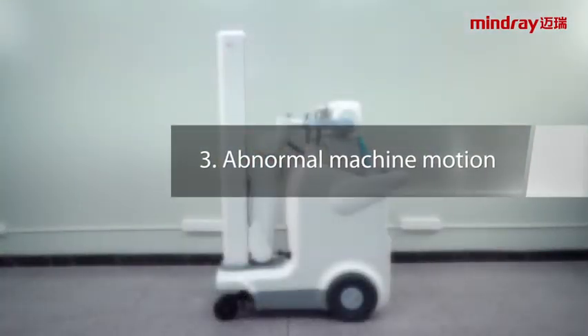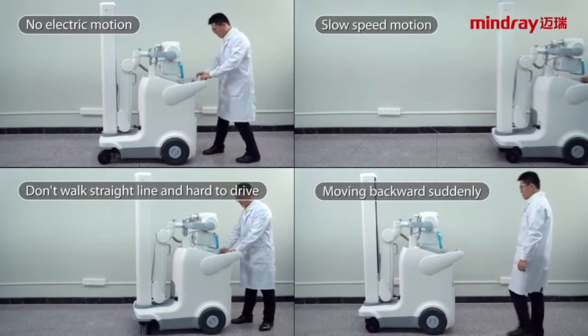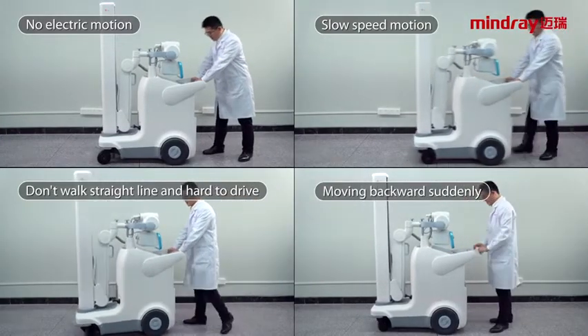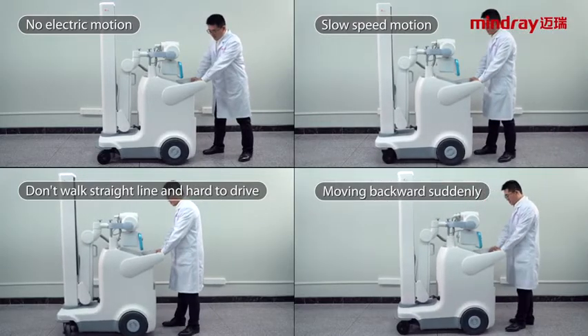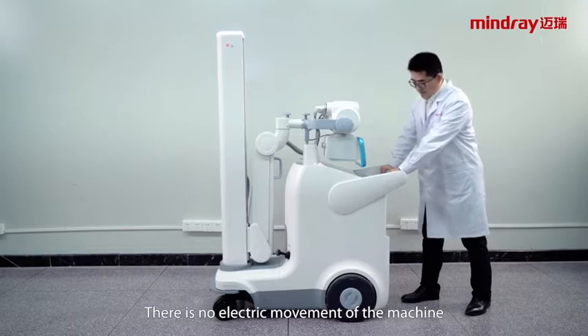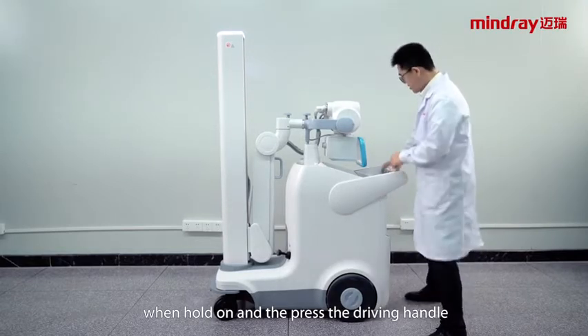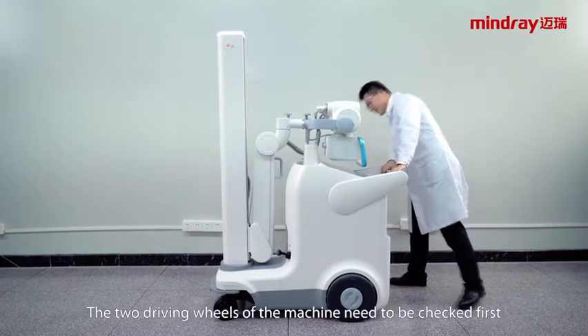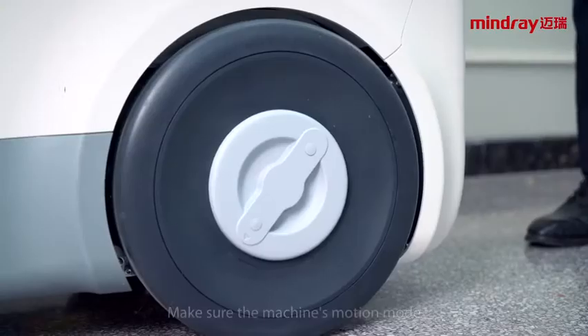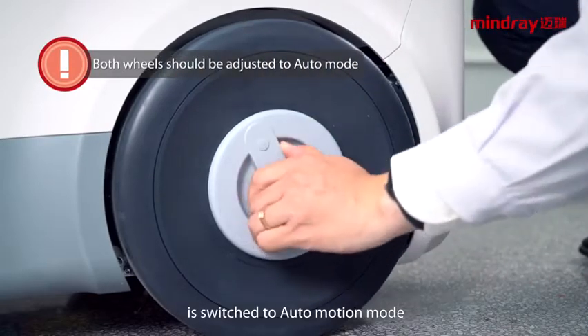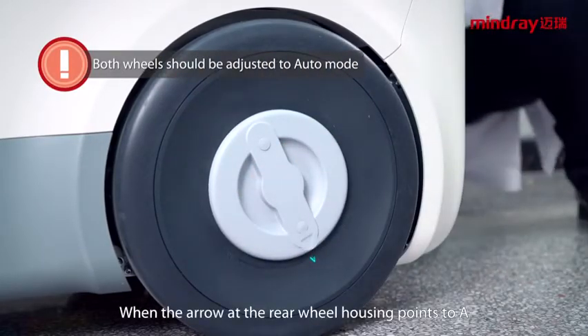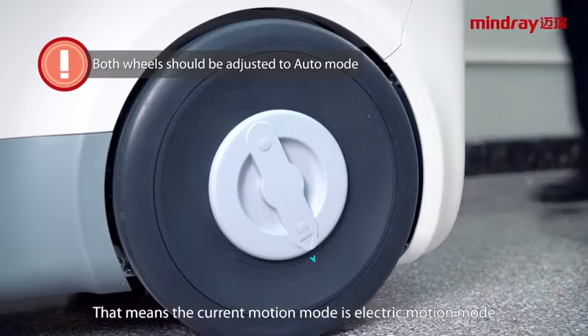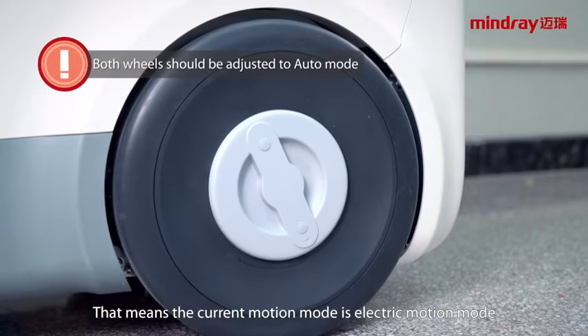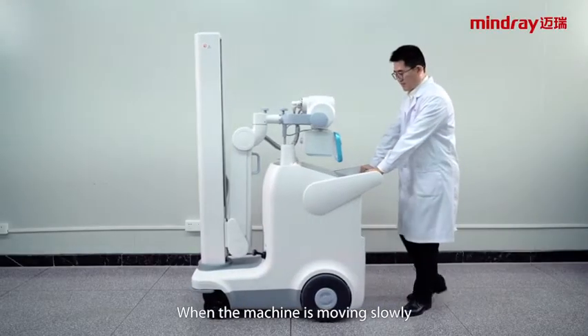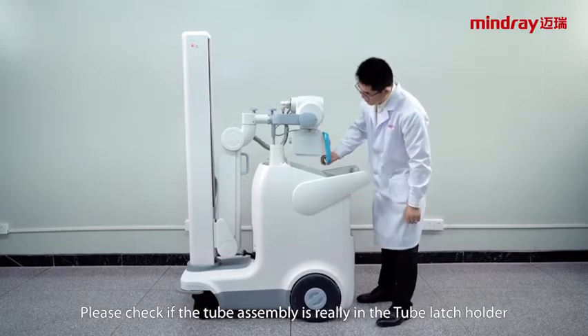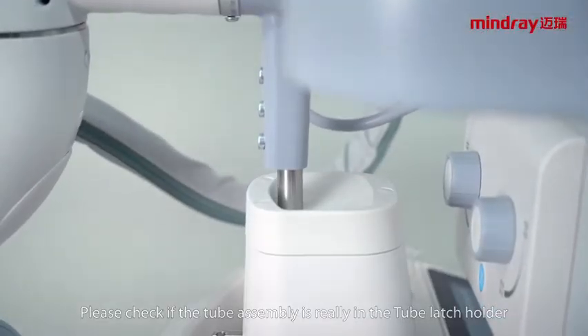Abnormal machine motion. No electric motion. Slow speed motion. Doesn't walk in a straight line and hard to drive. Moving backwards suddenly. There's no electric movement of the machine when you hold on and press the driving handle. The two driving wheels of the machine need to be checked first. Make sure the machine's motion mode is switched to auto motion mode. When the arrow at the rear wheel housing points to A, that means the current motion mode is electric motion mode. When the machine is moving slowly, please check if the tube assembly is really in the tube latch holder.